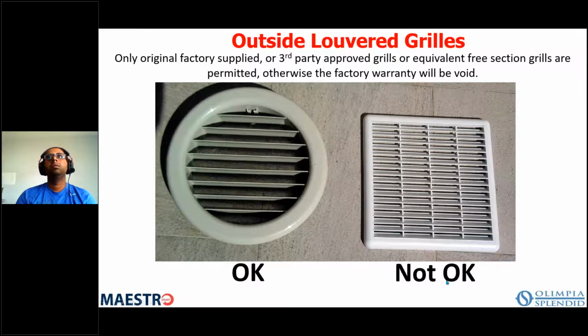And we always tell folks that you can only use a factory supplied grill or a third party grill that we have approved or have sourced, because this job was installed with this rectangular grill that did not have the surface area or free area that the unit originally had, and it would be tripping on high pressure because it wasn't moving enough air through the unit. So you can't just pick up any grill. We are currently working with a couple of manufacturers to get rectangular grills made. And we're looking at having two rectangular grills, just like you have two round, or we'll have one large grill that you would see. So we're trying to come up with a few different options.